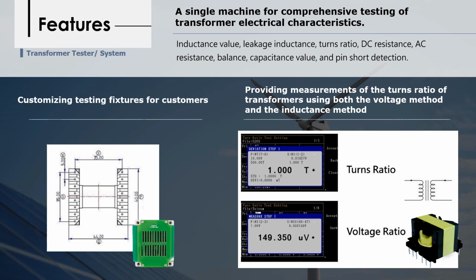Regarding turns ratio measurement, we provide two methods. Turns ratio measurement is crucial because it determines the relation between the input and output voltage of a transformer, enabling various voltage transformations. One is called the voltage method, where AC voltage is applied to the primary coil, and the AC voltage of the secondary coil is measured. This is done to confirm the turns ratio and phase relation between the coils. The other method is the inductance method, where the inductance value between coils is measured, and the turns ratio is calculated using the inductance values of the coils. This method provides more accurate results for transformers with significant leakage inductance.